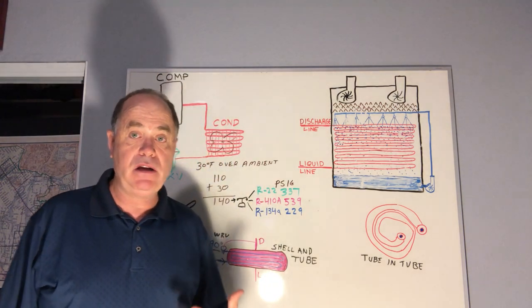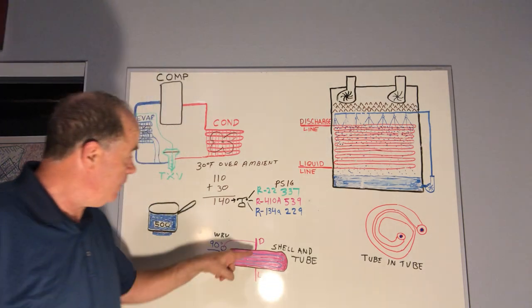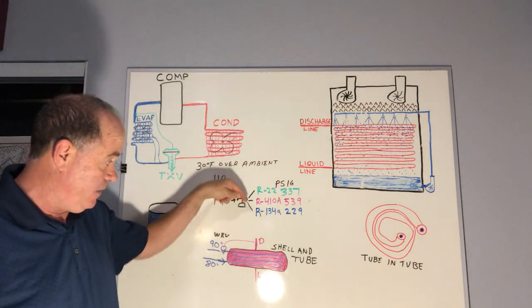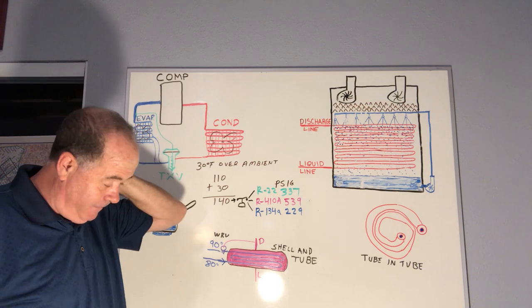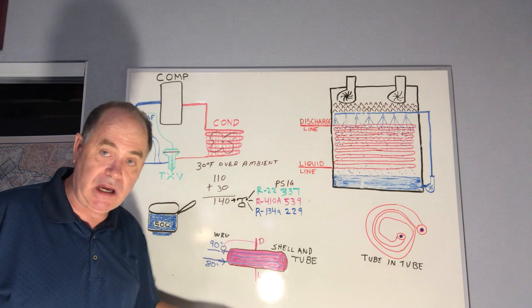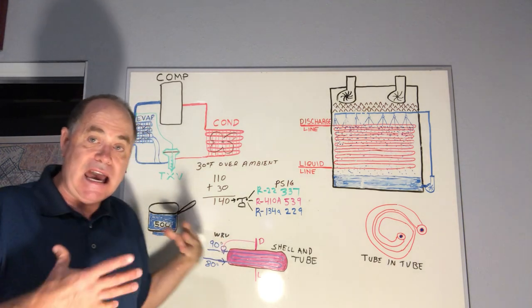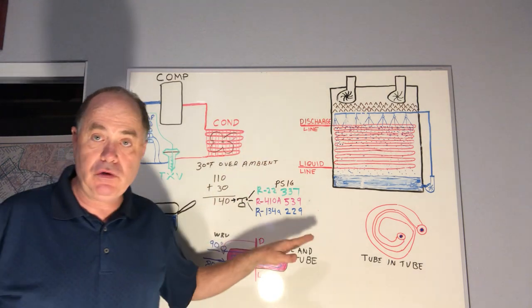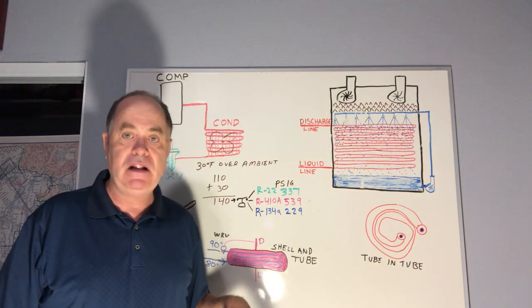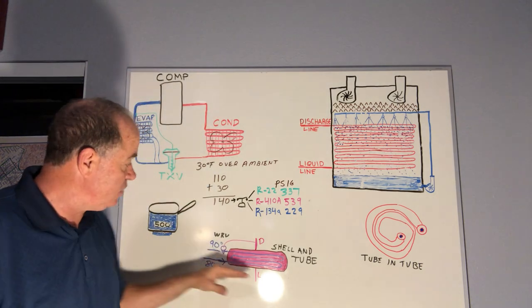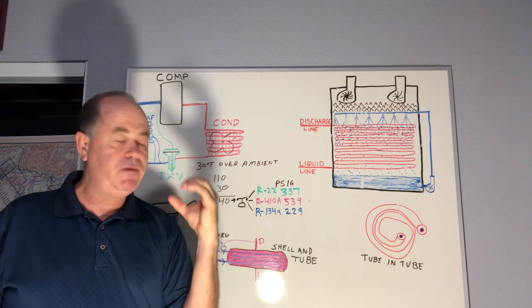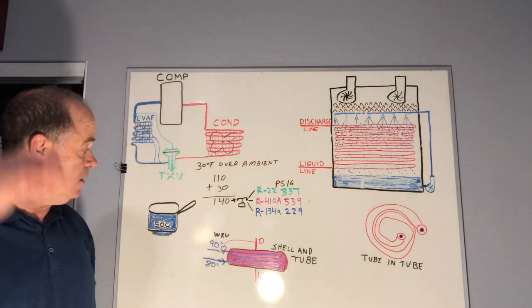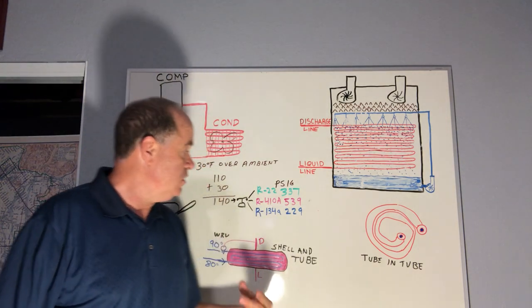To regulate head pressure in water-cooled systems, we use a water regulating valve tapped off the discharge line. As head pressure rises, it increases pressure on the water regulating valve, opening it more and letting more water flow through, which cools the condenser and drops the head pressure. If head pressure drops too much, the valve closes, reducing water flow so head pressure rises back up. The water regulating valve is constantly opening and closing just a little bit to maintain a steady head pressure — it's simple and effective.